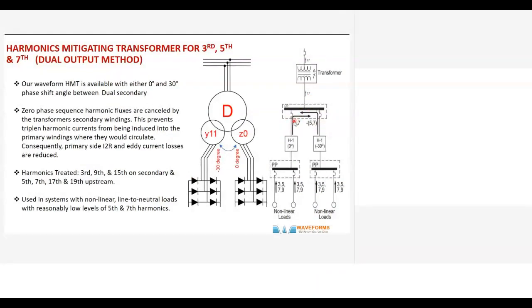So you can use it for data centers with 2 outputs for computers and all that. In some places in multi-story buildings, where you have data centers or instruments or things that need a high degree of protection, this transformer will be a little expensive. The only issue is it may not be that effective. It will be only 60 to 70% effective in filtering, and the imbalance will also cause some problems. It is also costly because it needs more space, and all these disadvantages will be there. But it will reduce the I2R losses and the eddy current losses, and it will improve the reliability of the equipment connected to it.